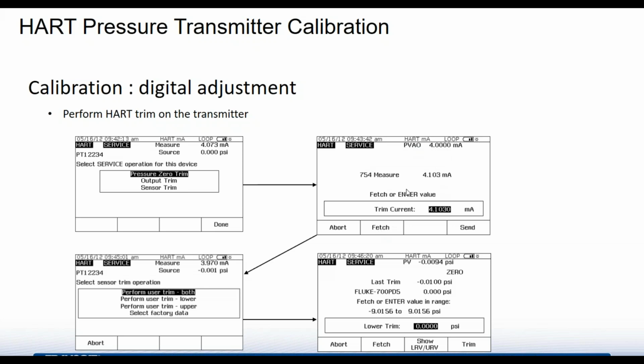So what you do is you fetch that value and you trim it so that it brings that back into that 4 milliamp specification. And then you'd go ahead and repeat that for the high end on the 20 milliamp. So now you've finished your 4-20 milliamp output trim.